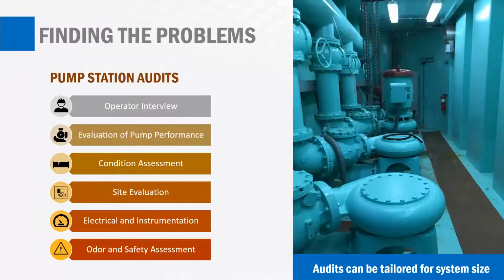So finding the problems, what do we do? Pump station audits are a great way to find the problems and really look at figuring out what to do about those problems so that you can manage those assets effectively. It really should start with the operator interview. These operators have some historical knowledge that engineers simply aren't going to have. Evaluation of pump performance. The pumps are why you have the pump station in the first place. It's a big deal to make sure that those pumps are performing properly. But it's also a big deal to look at your force main and make sure that the force main is working as intended.